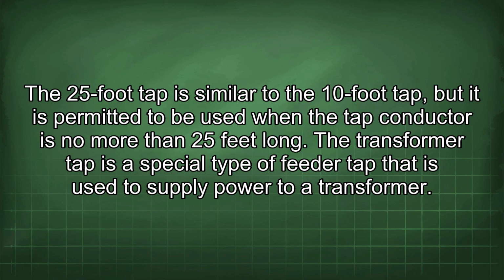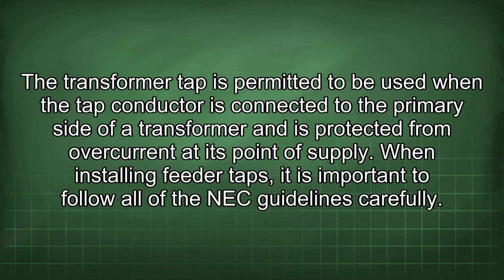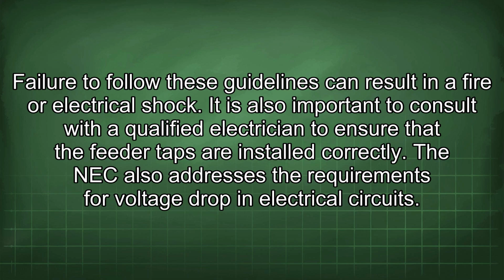The transformer tap is a special type of feeder tap that is used to supply power to a transformer. The transformer tap is permitted to be used when the tap conductor is connected to the primary side of a transformer and is protected from overcurrent at its point of supply. When installing feeder taps, it is important to follow all of the NEC guidelines carefully. Failure to follow these guidelines can result in a fire or electrical shock. It is also important to consult with a qualified electrician to ensure that the feeder taps are installed correctly.